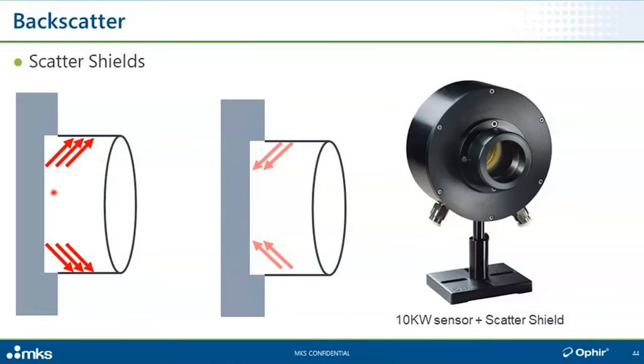Now, 90% of that will be absorbed and 10% of that will be backscattered. But okay, we've cut down the backscatter very significantly. Of course, the meter will need to know that the scatter shield has been added. There needs to be a separate calibration factor for the scatter shield in condition, because more light from that same beam is going to end up being absorbed by the sensor.